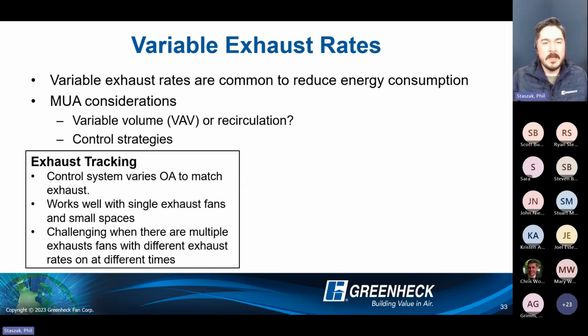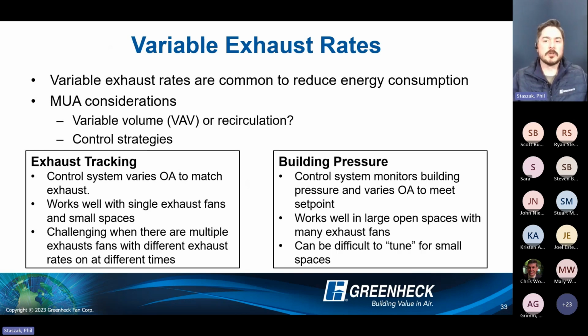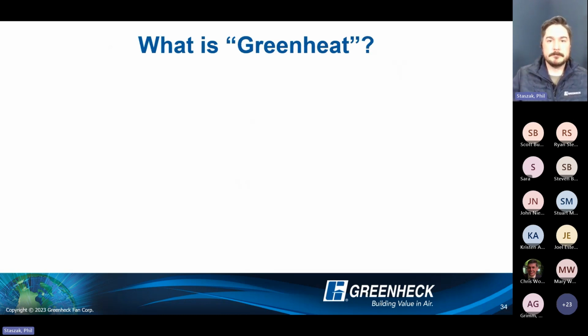So exhaust tracking is very common with single exhaust fan type systems, where we're just tracking: if this exhaust fan is on, or running at this speed, the supply fan will run at the same, typically for a more one-on-one type scenario. Now, building pressure control is more where you have open spaces. I mentioned the warehouse design, or if you have multiple exhaust fans, it's very easy to achieve a sequence. It's effectively changing the percentage or volume of outside air with a variable volume system, just based on a pressure setting instead.